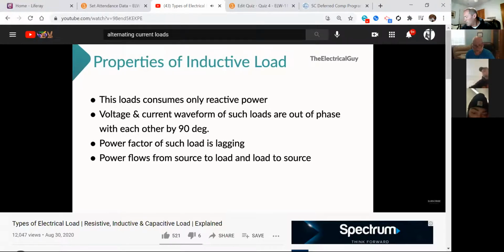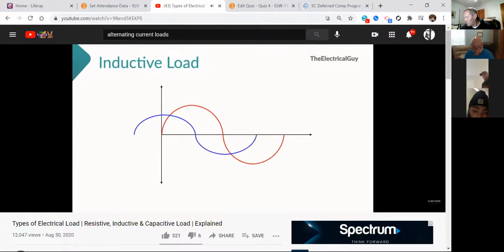This type of load is not as easy as resistive loads. They create a lot of problems in the system, but they are equally important. Since current lags behind voltage by 90 degrees in such loads, switching such load is difficult. As we know, circuit breakers open at current zero condition. If you look at the current and voltage waveform of such load, you will find that when current is zero, voltage is maximum, and hence when the circuit breaker opens at current zero, voltage across the breaker contacts is maximum. Whereas in case of resistive load, both current and voltage become zero at the same time. Therefore, switching such type of inductive load is one of the critical operations. Such type of load also affects the power factor of the system heavily, and hence electricity bill goes up.